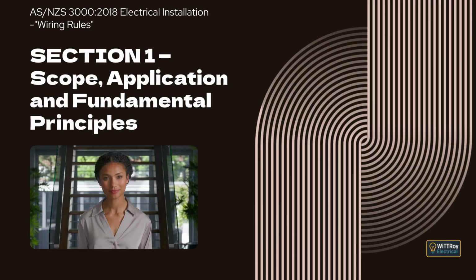Either situation can lead to serious harm, so the installation must be arranged to protect against both types. The second risk is excessive temperatures. Excessive temperatures can cause fires, burns, or other damage. People, equipment, and nearby materials must be protected from heat produced by electrical equipment, whether the heat comes from normal operation, fault conditions, or thermal radiation. The standard highlights three effects we must prevent: combustion or degradation of materials, risk of burns, and any reduction in the safe function of equipment.